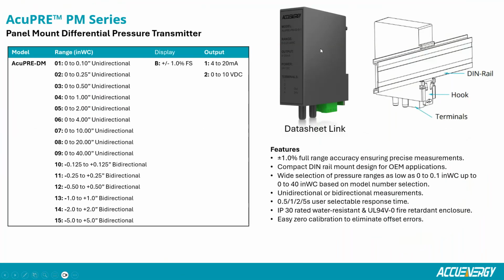And then we have our ACUPRE PM, which is short for panel mount. So this unit is a bit defeatured versus the duct mount and the wall mount unit. It's a very slim housing, and it gives you the ability of mounting it within a panel next to other components with very tight space constraints. And you just mount it to 35mm DIN rail with the integral DIN rail clip. It does not have an LCD. It does not have field selectable options. You have to know what your pressure range is prior to ordering. And it doesn't have the IP65 enclosure, but this is going to be typically mounted in a panel of some type. Yeah, that's the ACUPRE PM.